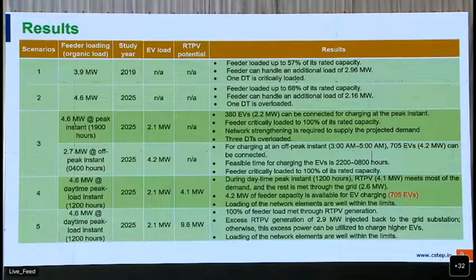Again, in the third scenario we did 2 more scenarios. One is what happens to the feeder loading during the peak instant, that means the peak organic load instant, and the other is the off-peak organic load instant. In the peak instant, the 4.6 megawatt remains the same. That is the peak load for that particular feeder in 2025. So the additional feeder capacity available is 2.1 megawatt. But in the off-peak instant, the additional feeder capacity available is 4.2 megawatt.